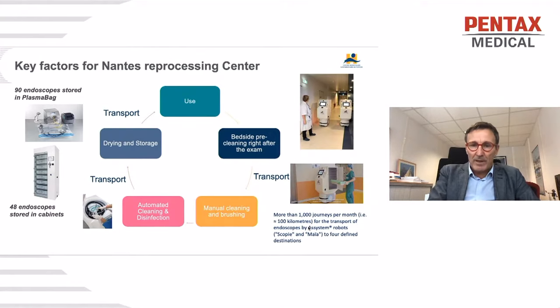Then manual cleaning and brushing, then automated cleaning and disinfection in a reprocessor, and then transport to store the endoscope. We are only able to store 48 endoscopes in our 6 cabinets because we have only 8 places per cabinet. We then need to store endoscopes with the plasma bag.